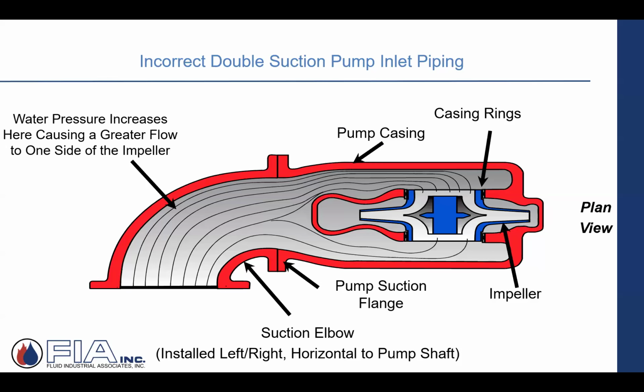This is kind of a picture of what you're not supposed to do. And it's just the don't part of it is how they took this elbow and just connected it right to the suction of the pump. And it's creating this greater flow, if you will, one side versus the other. What I just like is this part right here. This is the splitter. This is the casting inside that body that you can't see from the outside. And when it's done right, as that flow comes in, it will split evenly to one side as well as split evenly to the other. So you're evenly loading that impeller.